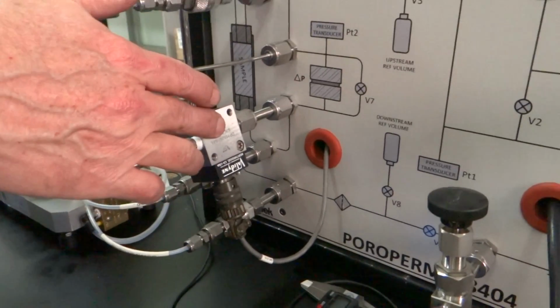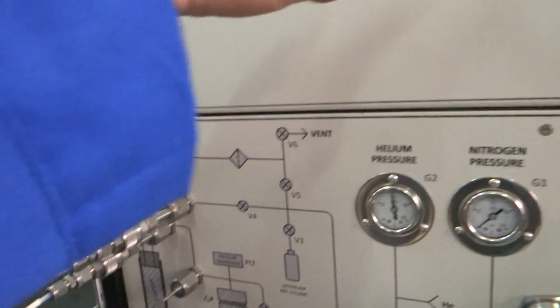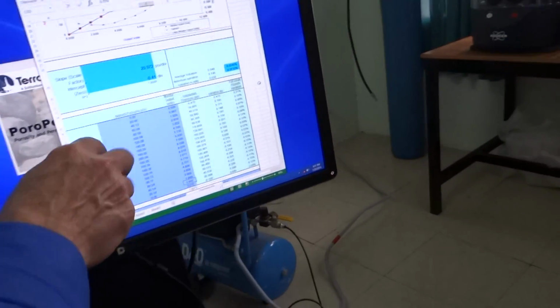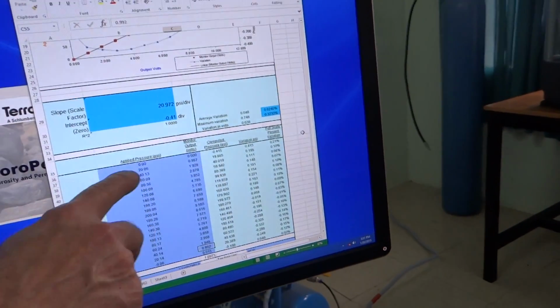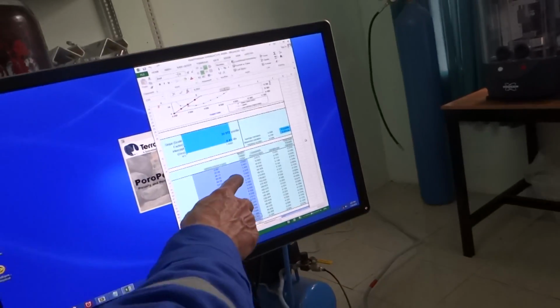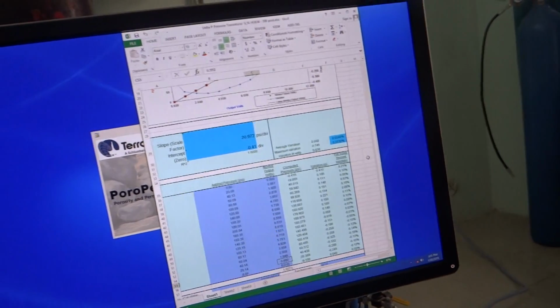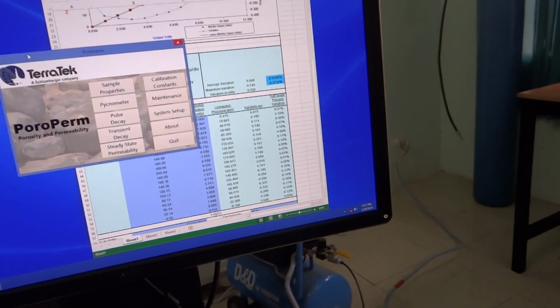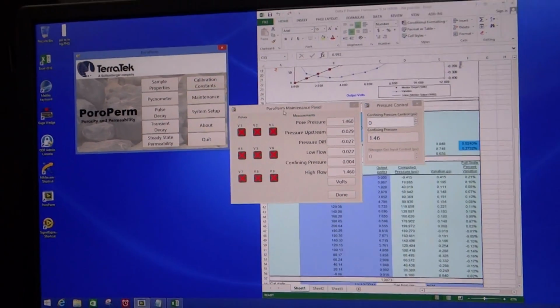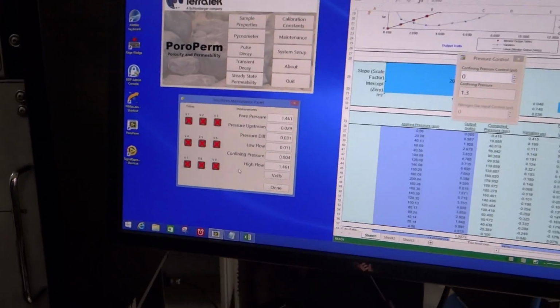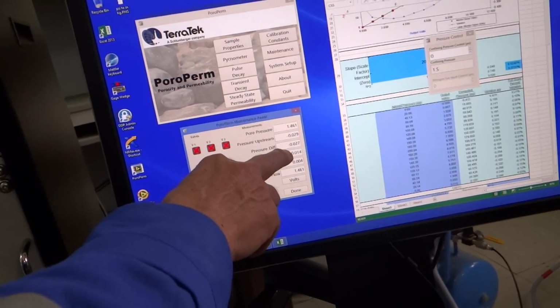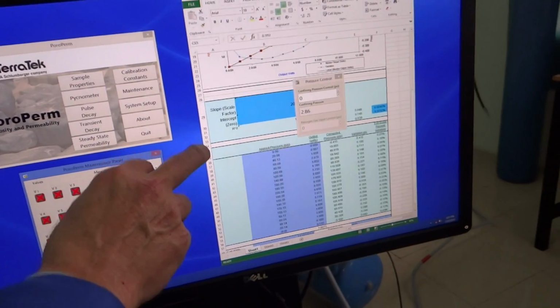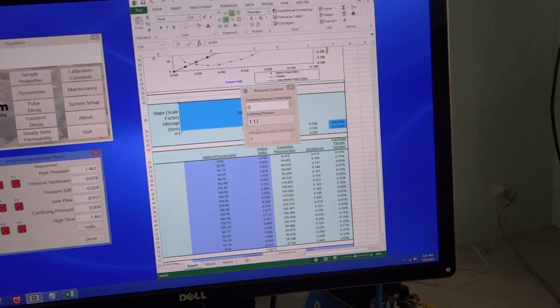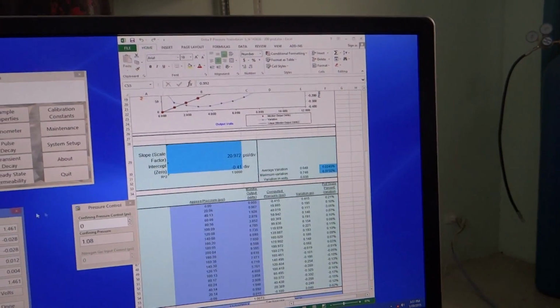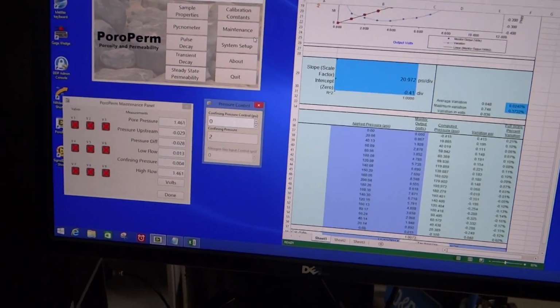Okay. When you calibrate the pressure transducers, you calibrate through this box and then you record the applied pressure, which will apply with this calibration, and you type in what the voltage out is, and you do that through the maintenance screen. So we'll be calibrating this pressure transducer.